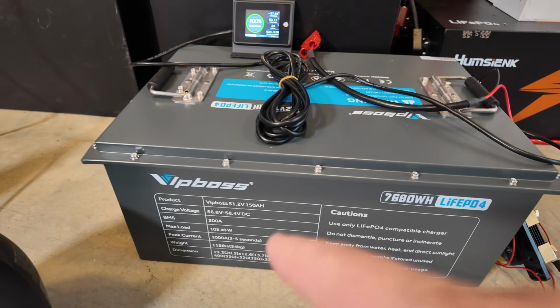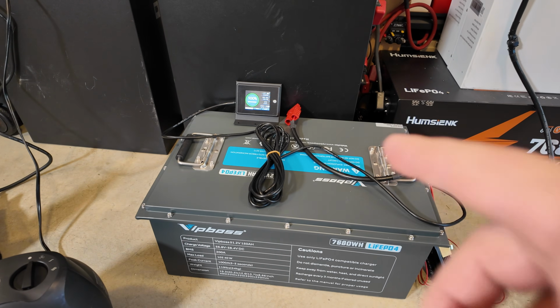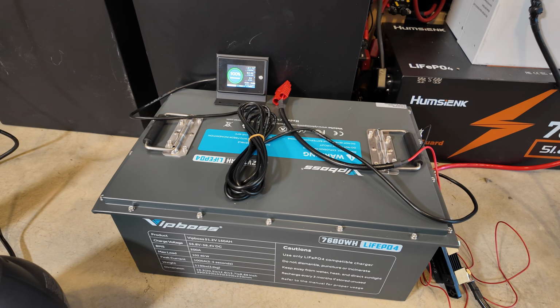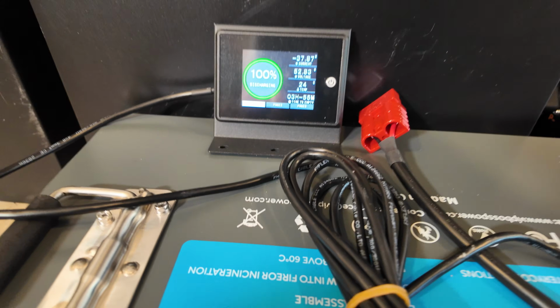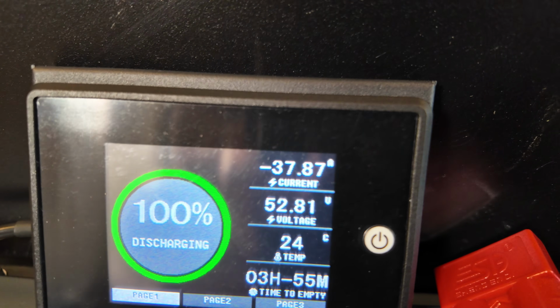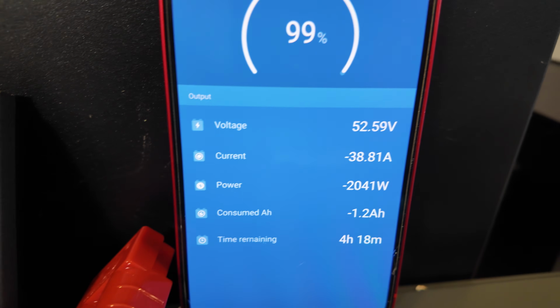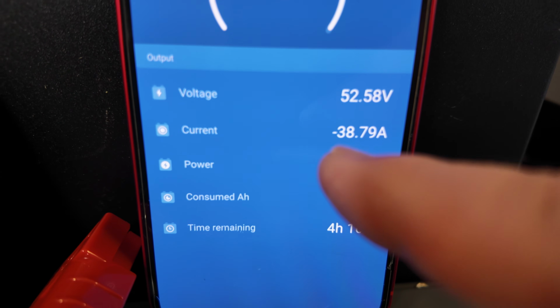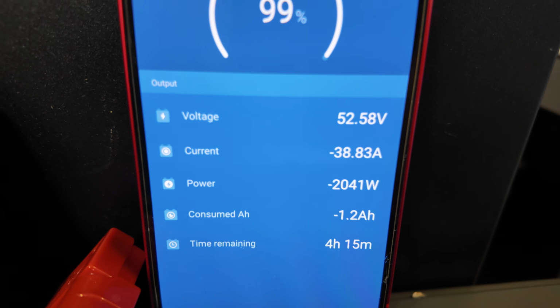Heavy load testing on the Vipboss. Now I know for sure I don't have enough loads to get this all the way up to 200 amps. I've already got one load running on it, and you can see we're pulling about 38-ish amps. I also have the Victron SmartShunt hooked up still, and it's saying almost 39 amps.